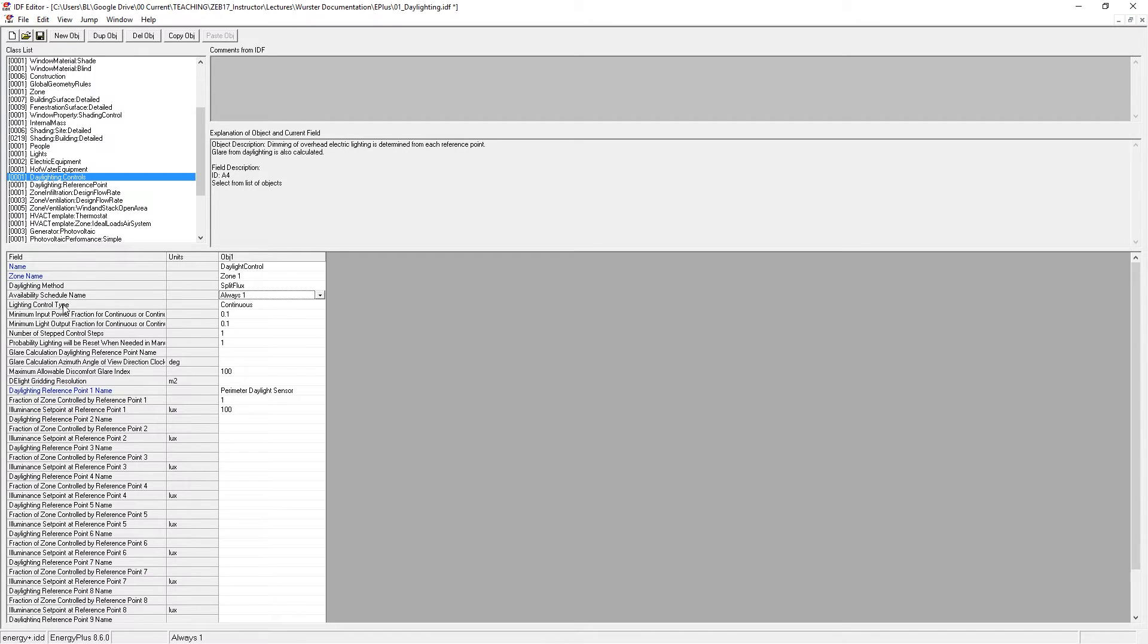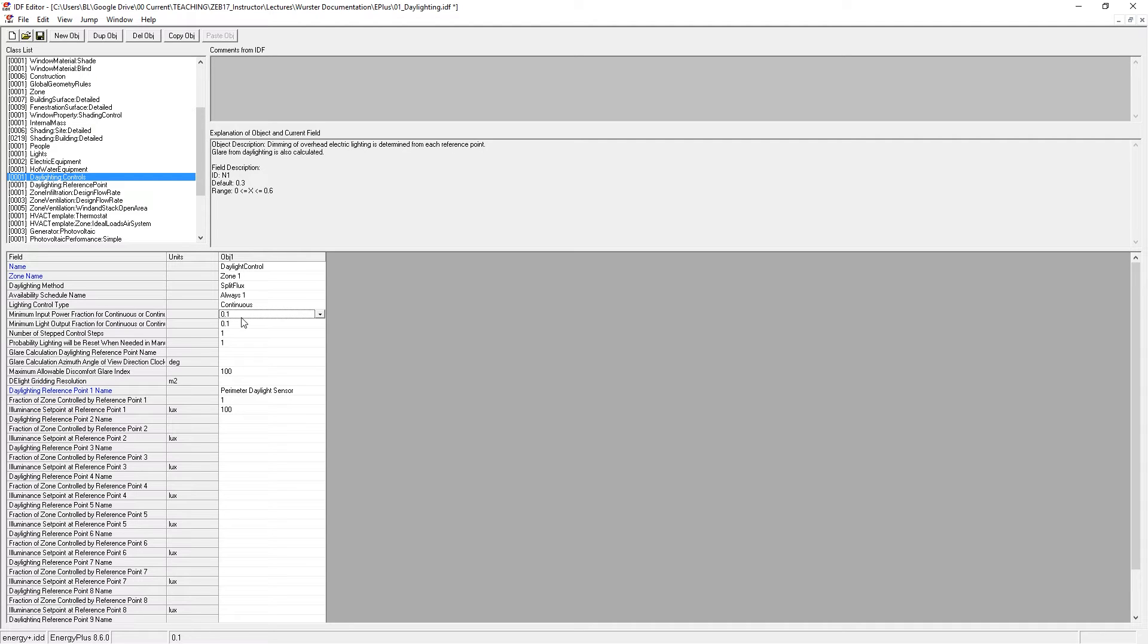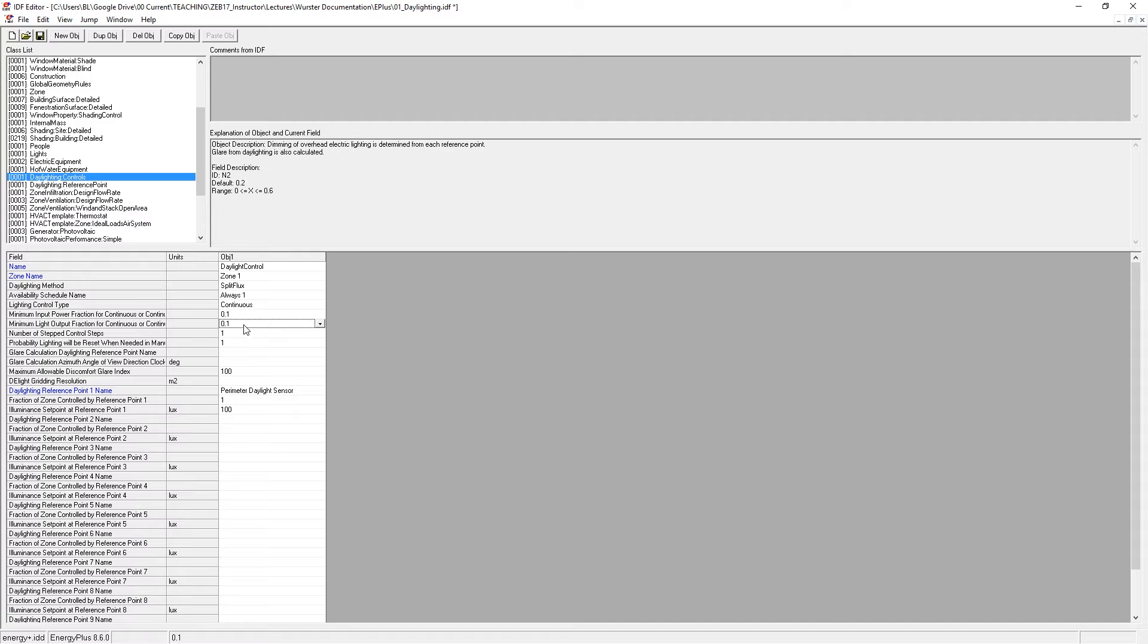The schedule I've got is always on. The lighting control type is continuous. This means that it's dimming continuously. The minimum input power fraction is 10% or 0.1. And the minimum light output fraction is 0.1. So that means that the lights will never dim below 10%, unless they go to off.